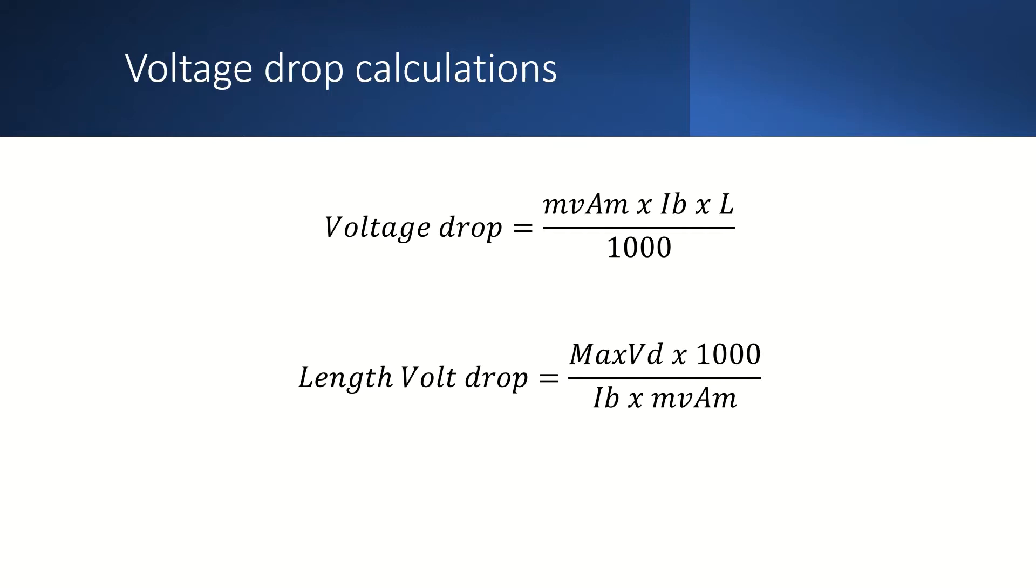So here we have the volt drop calculation from the on-site guide. The volt drop can be calculated by multiplying the value of millivolts per ampere per meter by the design current and the length and then dividing by 1000.